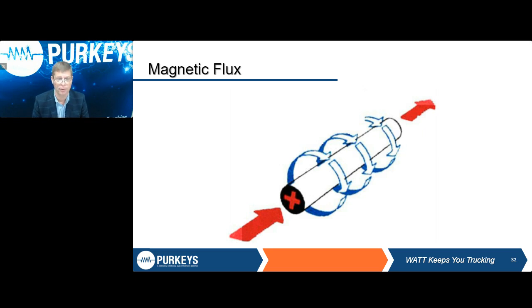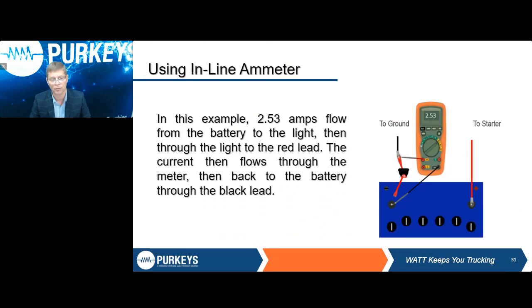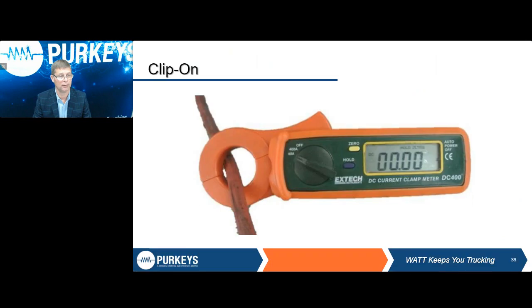But on the screen right now, you see an example of the right-hand rule of electricity. This is a positive cable. If I put my right hand on that cable, I put my thumb in the direction current flows, look at the way your fingers wrap around that wire. That is the way that magnetic field is generated. So if you're using a clip-on amp meter, which we'll show you here, oops, I got some slides out of order here. This is a clip-on amp meter. If you notice, it just clips around the cable and it generates that magnetic field.